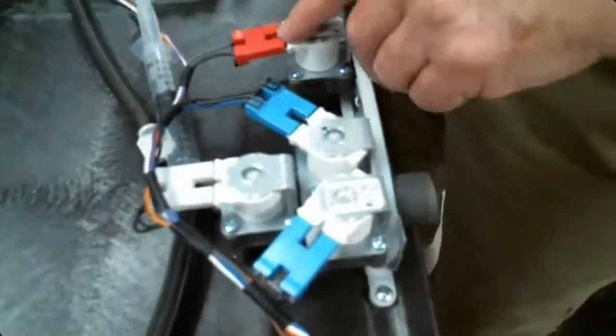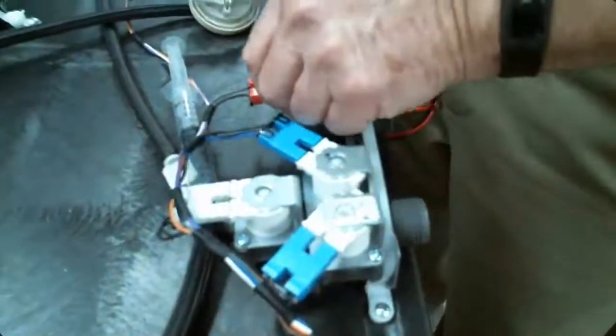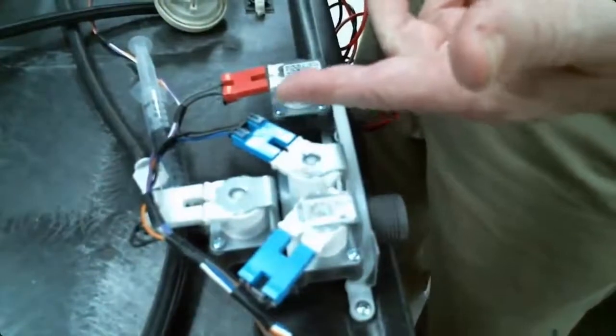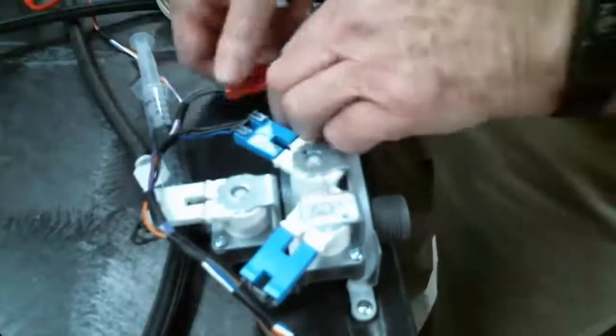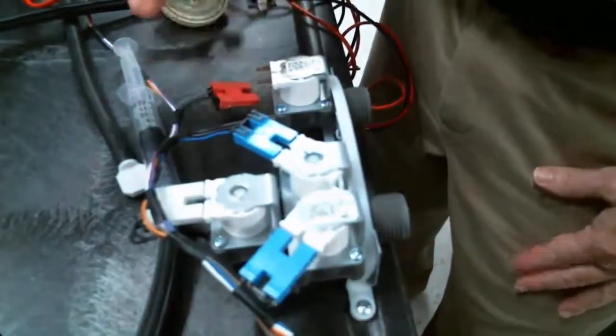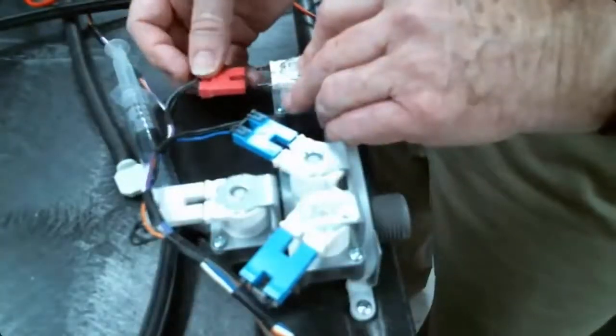So just don't always assume that because it's working in test mode, it's going to work in a normal cycle. Now, if you pull these connections off of here, a 9-volt battery will actually energize these things. Once again, it doesn't always guarantee that there still isn't a problem with these valves, but we can test them with the 9-volt battery.